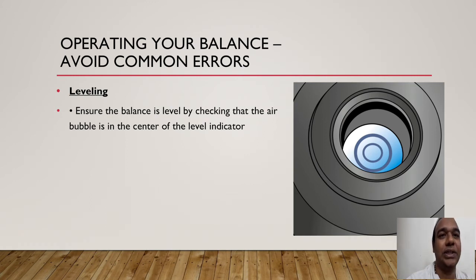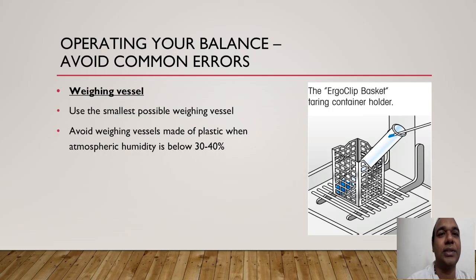Ensure the air bubble is in the center of the level indicator before proceeding. Regarding weighing vessels, use the smallest possible weighing vessels. ErgoClip baskets are available and have very low weight — you can see them in the slide. Avoid weighing vessels made of plastic when atmospheric humidity is below 30 to 40 percent — how this affects results will be covered in a later slide.